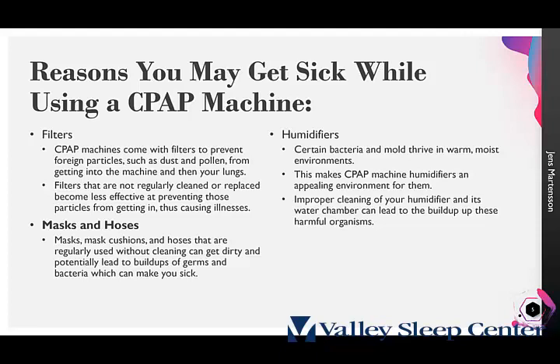Humidifiers are the next item you'll run into. The humidifier has water in it, and generally you want to change that water out daily. The water heats up, and heat and humidity can facilitate bacteria and fungus. If you're not cleanly washing your tank, it can have a film buildup around it, almost a slime. Some of these water tanks have gaskets that need to be cleaned out appropriately.